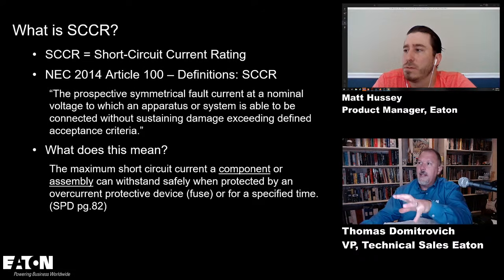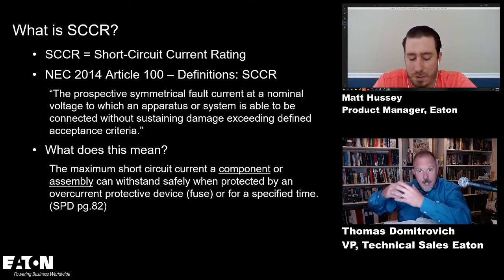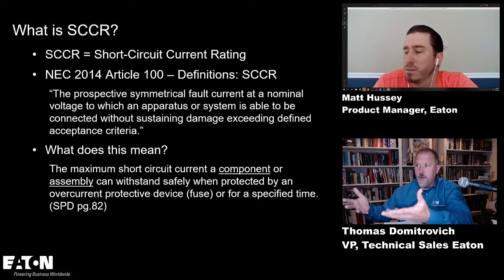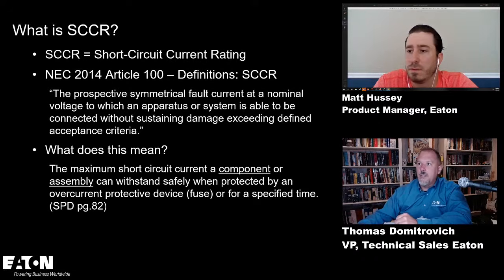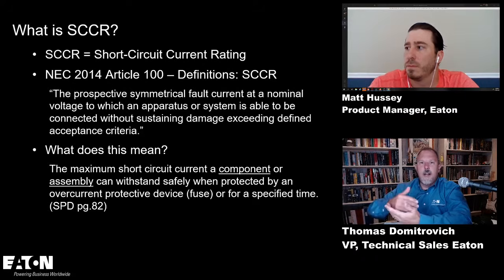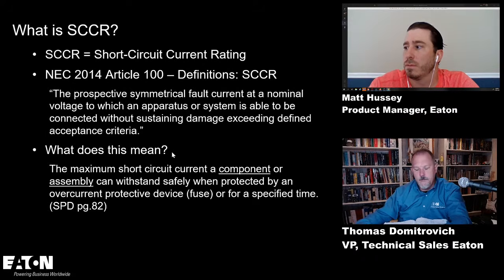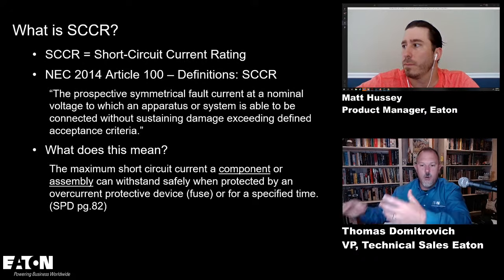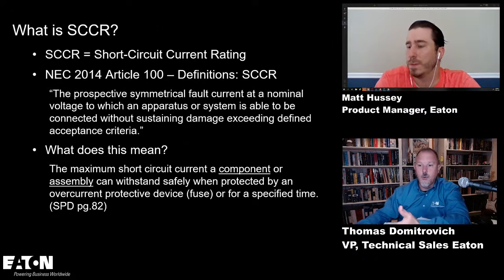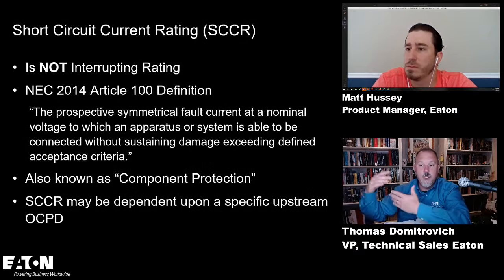So short circuit current rating is the ability for that to, we only got 10 minutes left. So the short circuit current rating is the ability of the equipment to pass through the fault current, to let it pass through, not stop the fault from flowing, but to let that pass through. And there's a definition in Article 100. It's not an interrupting rating. It is the rating of the motor control center that basically you can hold it together under the magnetic forces of the fault current passing through it to the load.